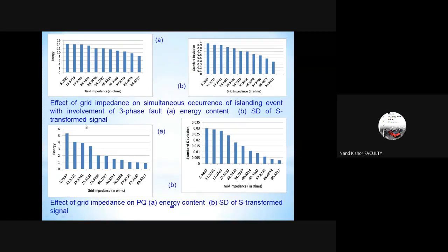Similarly, we have the study of grid impedance for which we consider the simultaneous occurrence of an islanding event with a three-phase fault. And even for these different kinds of event occurrence, the variation of energy and the standard deviation do not cross the threshold that we have considered in the design here.